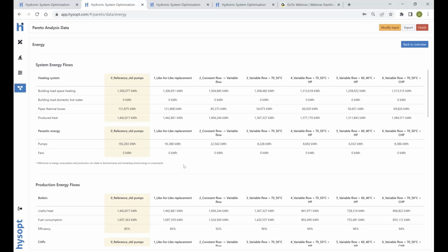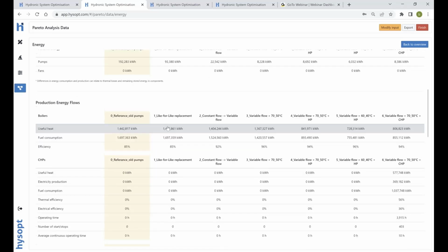So those 20 pumps were eliminated in the optimization, and the new pumps are no longer a like-for-like replacement, same with the boiler, but they are again sized towards the system which they had been operating for the last 5 years within the optimizations, which also means smaller pumps being installed.